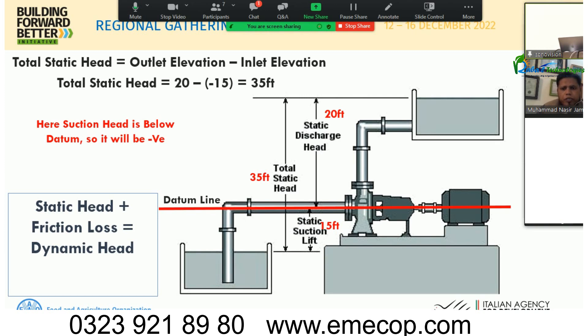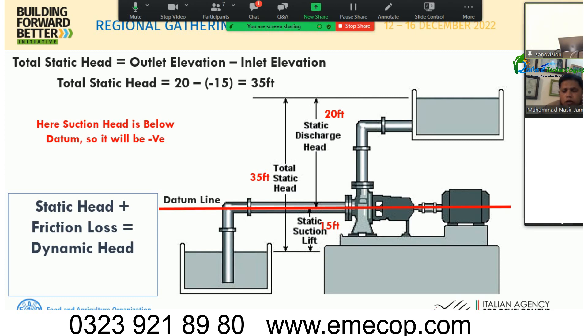For a quick refresher on static head: the datum line is shown in red. When water is sucked from below the datum line, we add up the suction lift and discharge head. With suction lift of minus 15 feet and discharge of 20 feet, the total static head is 35 feet. Total dynamic head comes from adding friction losses to the static head.